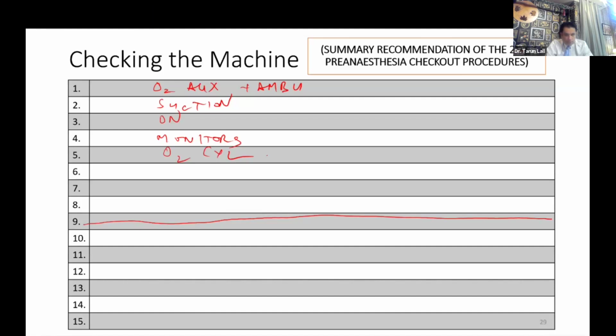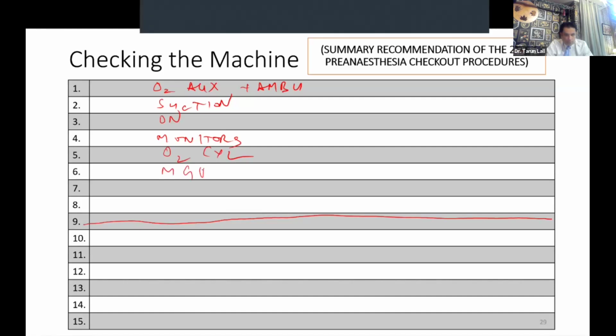After the oxygen cylinder, high pressure, I come to the intermediate pressure. So what is the intermediate pressure? It is your medical gas pipeline system. Pressure should be 40 to 60 psi. And I will also do the tug test and see that all the connections are secure. There are no loose connections from the wall. And this will hold steady when I start my case.